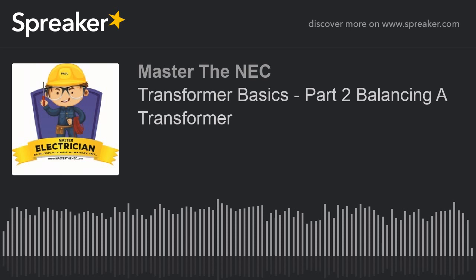We're going to work at this because I'm going to tell you that the little values are probably not going to make that much of a difference when you're selecting the overall kVA of this transformer. It shouldn't make that much of a difference, okay? All right. And it could put you on a borderline, but I just need you to understand that in some cases, you're not going to get an even division.